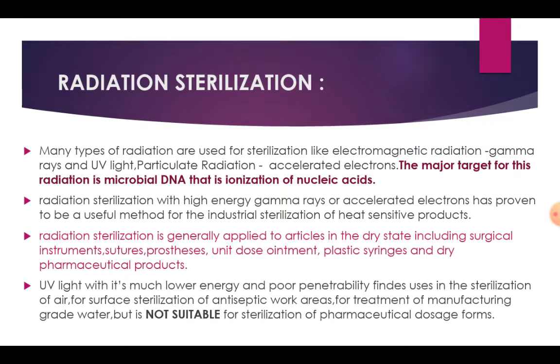Radiation sterilization. Many types of radiation are used for sterilization, like electromagnetic radiation, gamma rays, and UV rays. Particulate radiation, accelerated electrons. The major target for this radiation is microbial DNA, that is, ionization of nucleic acids. Radiation sterilization with high energy gamma rays or accelerated electrons has proven to be a useful method for industrial sterilization of heat sensitive products. Radiation sterilization is generally applied to articles in the dry state, including surgical instruments, sutures, prostheses, unit dose ointments, plastic syringes, and dry pharmaceutical products.